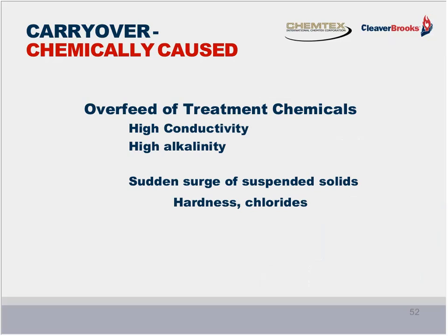While these are very common things to see, you can see there's a lot of different opportunities to cause carryover in a boiler. Certainly from a chemical treatment standpoint, high conductivity can cause carryover, high alkalinity can cause carryover, or a sudden surge in suspended solids from high hardness or high chlorides entering a boiler from a malfunctioning pretreatment system, bringing a bunch of salt water into the boiler, can increase the suspended solids of the boiler and cause carryover from that.